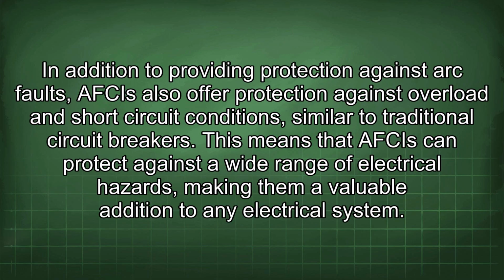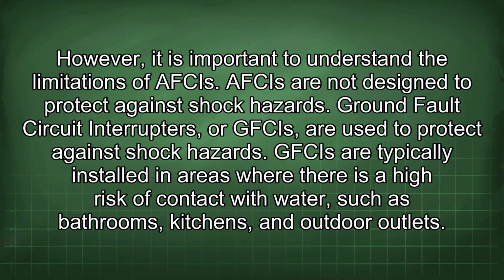In addition to providing protection against arc faults, AFCIs also offer protection against overload and short-circuit conditions, similar to traditional circuit breakers. This means that AFCIs can protect against a wide range of electrical hazards, making them a valuable addition to any electrical system. However, it is important to understand the limitations of AFCIs. AFCIs are not designed to protect against shock hazards. Ground fault circuit interrupters, or GFCIs, are used to protect against shock hazards.